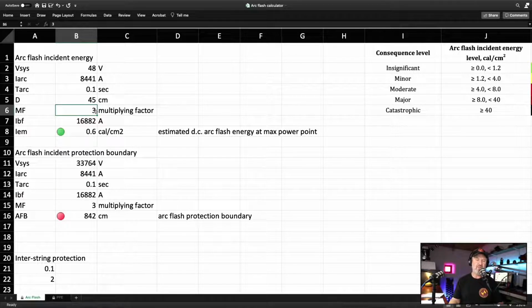Now, the other problem is the multiplying factor, which you really can't do much about. If the battery system is outdoors, in open space, it's 1. If it's in a room, it's 1.5. If it's in an enclosure, it's 3. And this battery system is in an enclosure, so it is 3. So there's not much we can do about that.